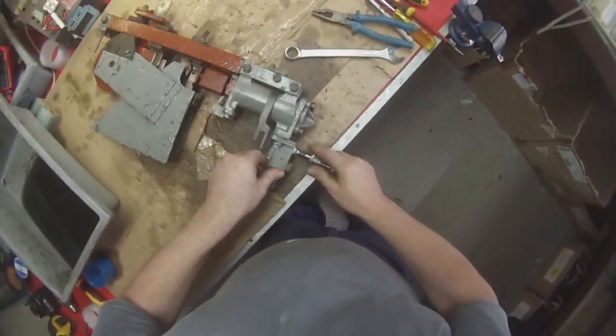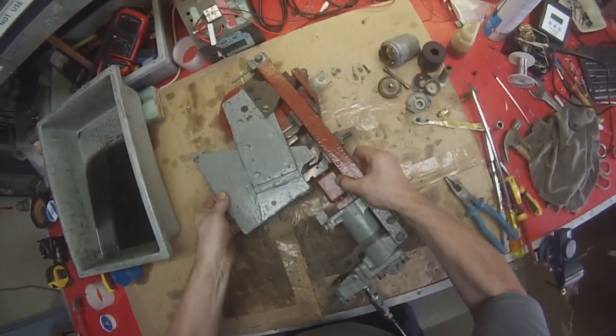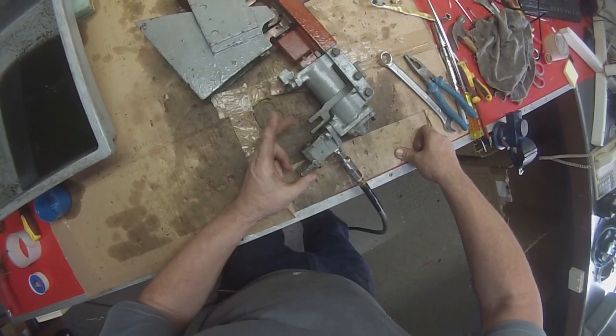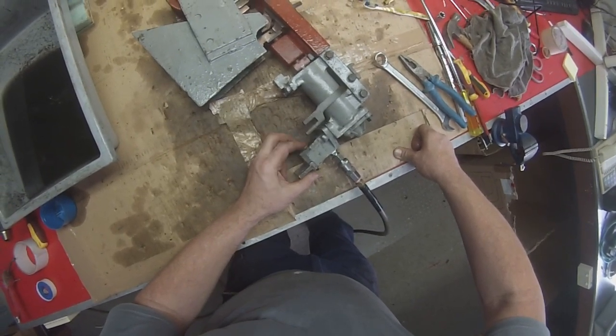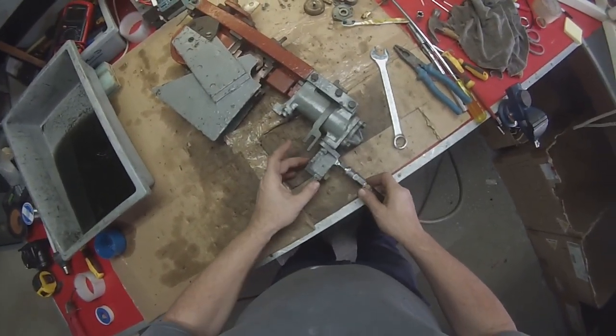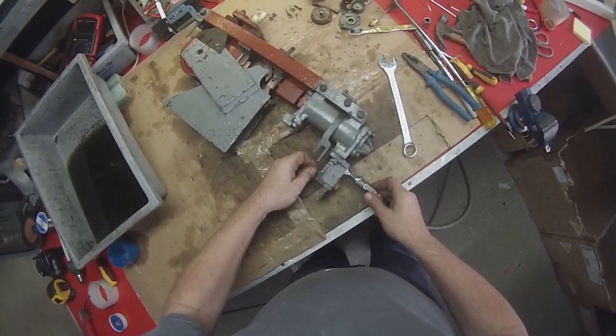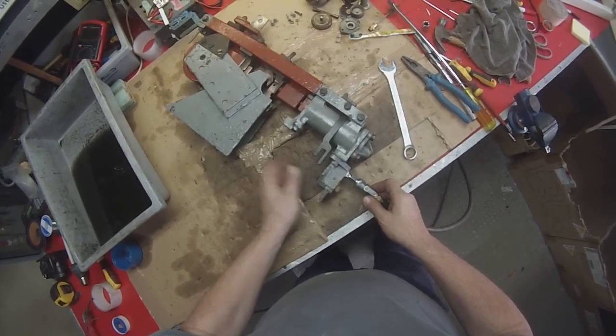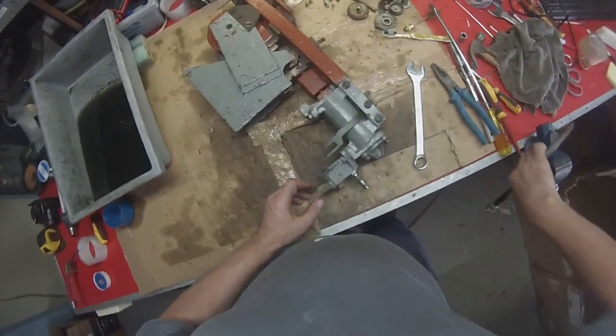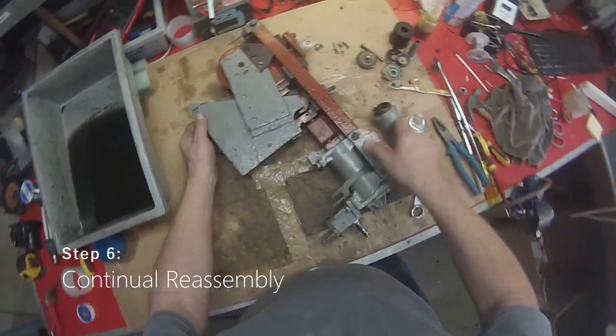And as you can hear, there is a little bit of blow past on the off valve. Not much. Okay, let's try it out. That's a leak on this thing. Okay, I'm going to pass that. So we shall pass that one, leave it as it is, and assemble the rest of the valve.